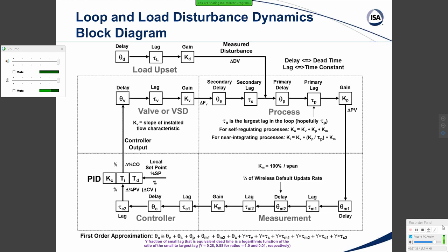Oh yeah, and also PID execution. We've mentioned this before in previous webinars, and Michel Ruel did it as well in his webinar, how important it is to recognize the dead time. That gives you a key as to how you can set different things associated with PID and the measurements, and whether your valve is too slow, or your measurement is too slow, all those things.